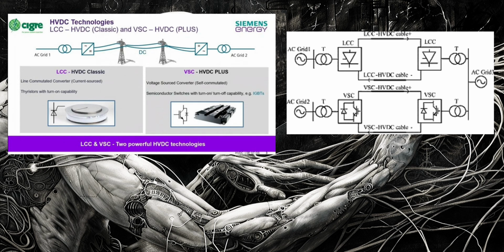After the development of more advanced utility-scale power converters, DC transmission became an option for humanity. A proper converter can change the DC voltage potential to whatever is needed. There are two main types of HVDC converters: the line commutated converter, or LCC, and the voltage source converter, or VSC. The key difference in converter type is the semiconductor used. LCC uses thyristor valves, while the VSC uses IGBTs.